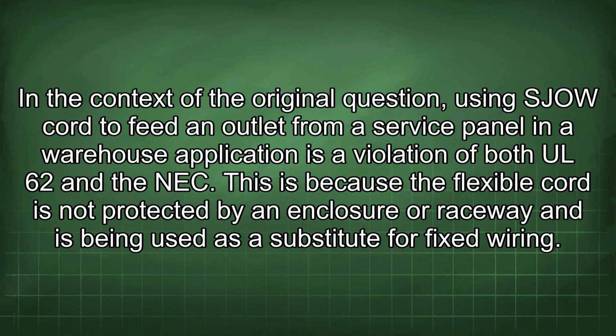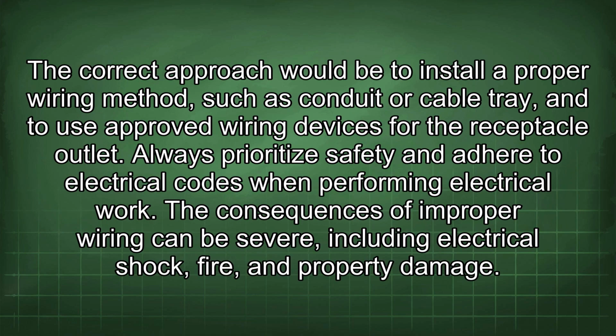In the context of the original question, using SJOW cord to feed an outlet from a service panel in a warehouse application is a violation of both UL 62 and the NEC. This is because the flexible cord is not protected by an enclosure or raceway and is being used as a substitute for fixed wiring. The correct approach would be to install a proper wiring method, such as conduit or cable tray, and to use approved wiring devices for the receptacle outlet.